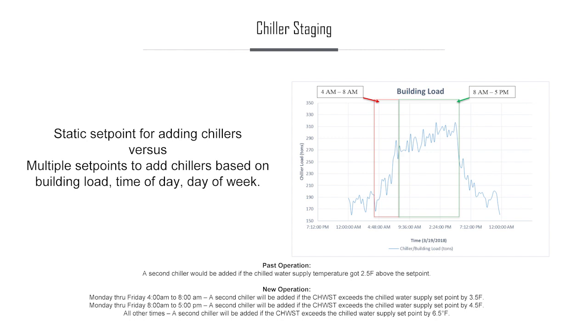By watching and observing the building over time, and that's literally being in the building and watching it do its daily cycle through the summer, it became apparent that the second chiller, and this is North Alabama in the summertime, was slamming on at right around 3 o'clock in the afternoon. Then right about 3:30, everybody's walking out the front door, and that chiller would carry on for a little bit until it hit its threshold to destage, and then it would stage off.